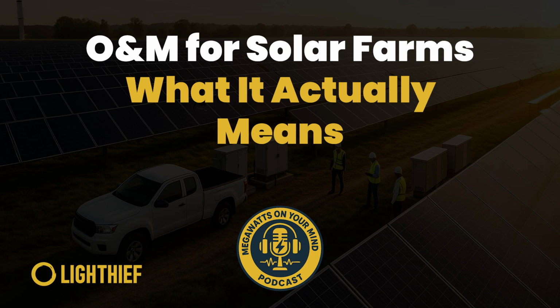For inverters, there's a separate maintenance schedule. Inverters are the only active electronic components in most solar farms, and they require attention. Filter cleaning or replacement, fan maintenance, cooling system checks, firmware updates, capacitor testing. Many inverter manufacturers specify maintenance requirements in their warranties. If you don't follow them, your warranty becomes void. So, this is both a performance issue and a contractual obligation. Trackers, if you have them, need mechanical maintenance, lubrication, motor testing, controller calibration, checking for structural issues. Trackers add performance, but they also add maintenance complexity.